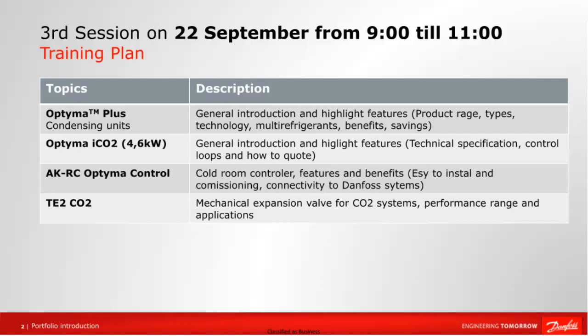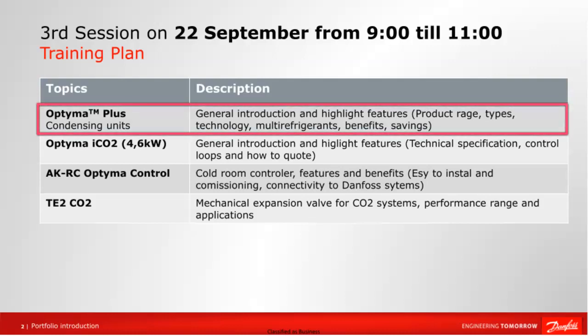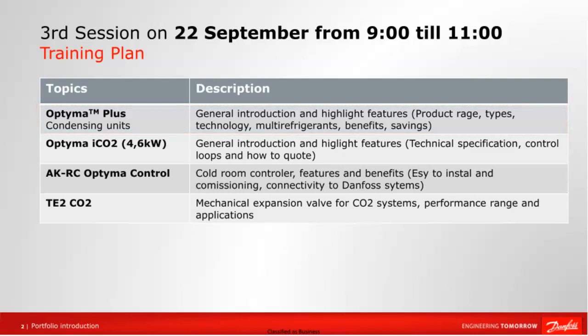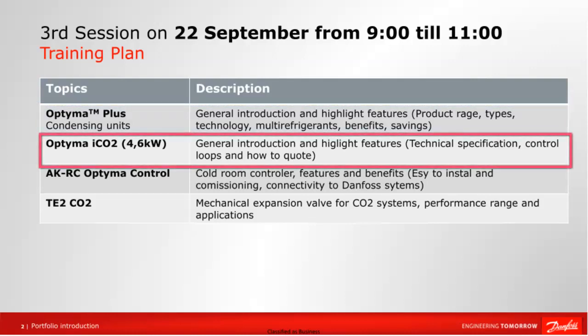I will start by discussing the Optyma Plus Series Units for use with standard refrigerant as well as with class A2L refrigerants, example with a very low GWP coefficient refrigerants. I will discuss the range of products and their features and benefits. In the next part, I will discuss the iCO2 4.6 kilowatt unit for application with the natural CO2 refrigerants. I will discuss the technical specifications of this unit and what to pay attention to when bidding.